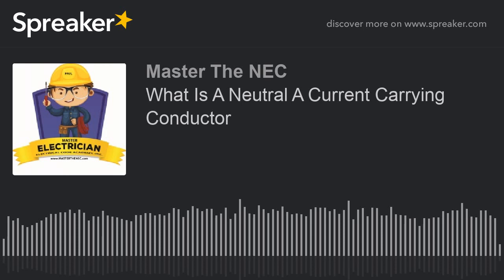So in your National Electrical Code book, if you're following along, you're pausing, whatever, catching up, then you really want to go to 310.15(B)(5). Now, that consists of an (A), (B), and a (C). The first one is dealing with, and we'll talk about it, where you're dealing with a neutral conductor that only carries the unbalanced current from other conductors. And I'll give you an understanding so you kind of get it.